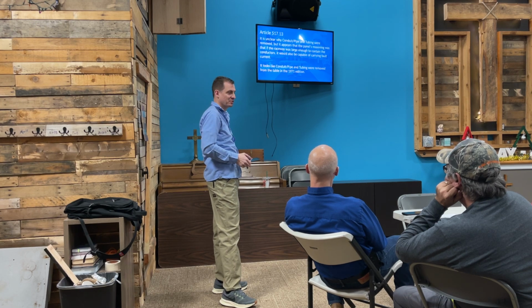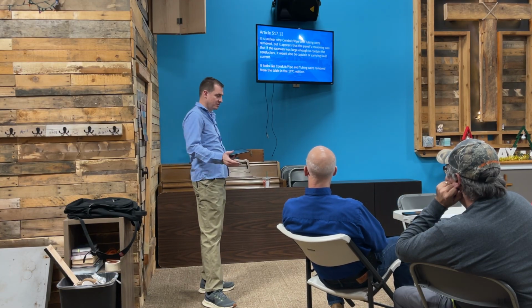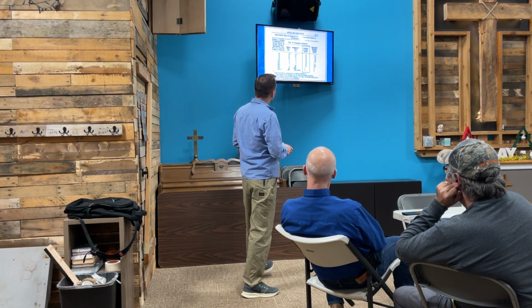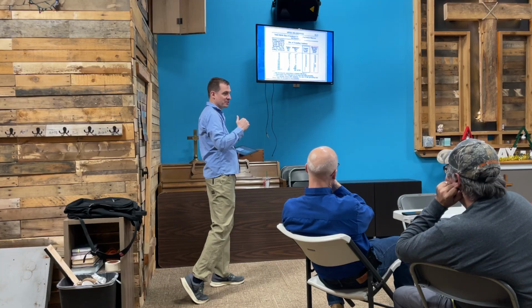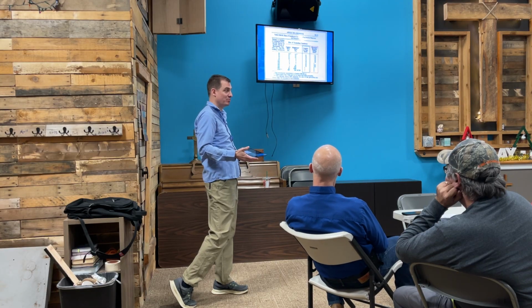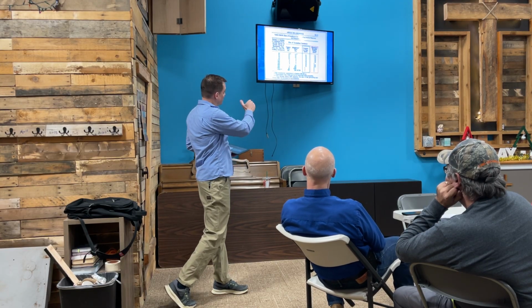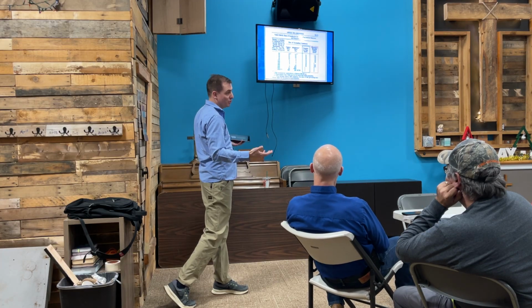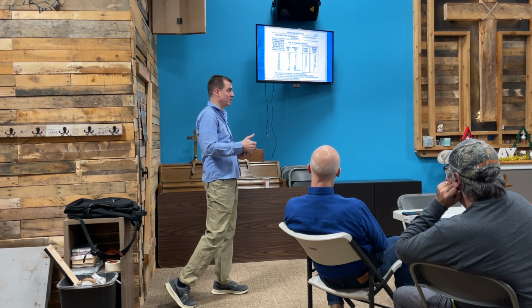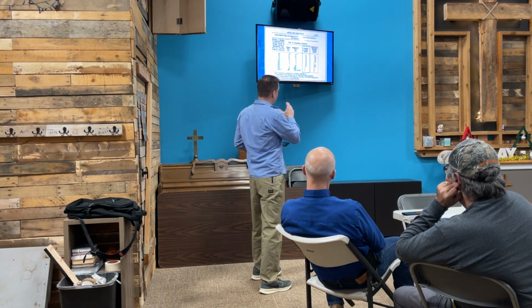That seemed to be some of the substantiation behind this. Why was this chart pulled out? If it could handle the conductors, it can handle the fault. If they were using the raceway as a ground, so let's go back to the 1/2-inch. You're only going to be able to put a certain size conductor in that before it physically won't fit anymore. So you're not going to be able to get a 200 amp circuit. Check your pipe fill too. It doesn't matter if it's on a 200 amp circuit, because the raceway is too small to ever get those conductors in it.